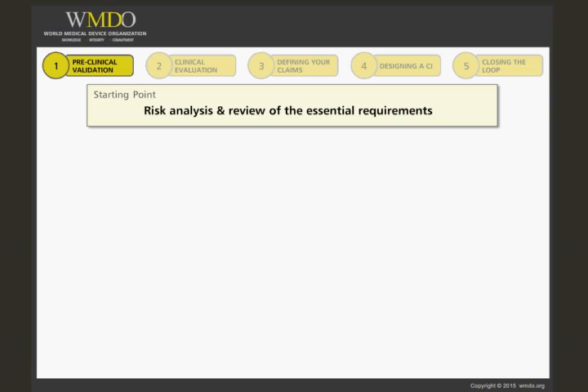An example of such a checklist that adheres to the Medical Device Directive and the Active Implantable Medical Device Directive is provided in your course room. From the risk analysis, you will have identified a number of risks and possible means by which you can minimize these risks so that they do not outweigh the benefits to the patients. As seen in previous courses, several design criteria must be taken into account.